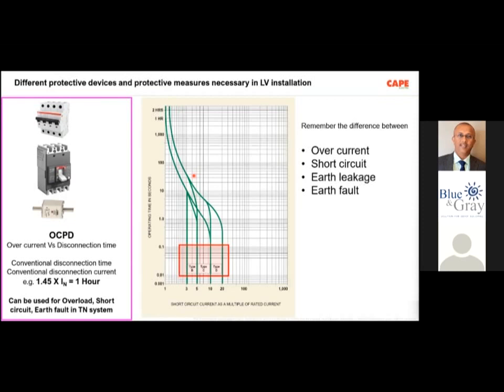The MCB does not have to trip up to 1.13 times the current, that means 11.3 amps. If the current is up to 1.45 times the rated current, it can take up to 1 hour to trip. So basically, these protective devices are used for two purposes. Very important to understand these two purposes. The first purpose is that these protective devices are to protect the wiring and the circuit. This means it is not to protect your equipment, because your equipment is supposed to have its own protective measure against overcurrent and short circuit. Now, the first job of these protective devices is to protect the circuit, number one, and in case of any earth fault, these devices are supposed to protect against a shock voltage. So two purposes are served by the OCPD.